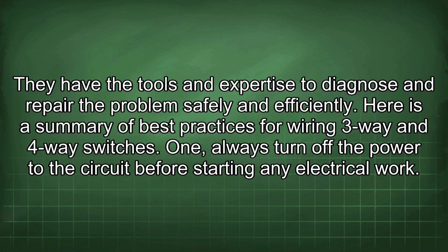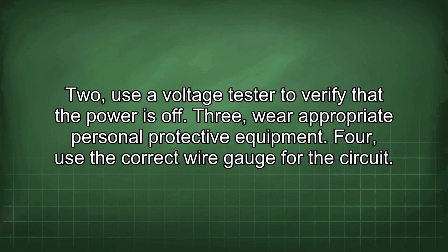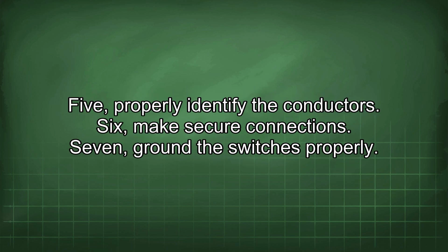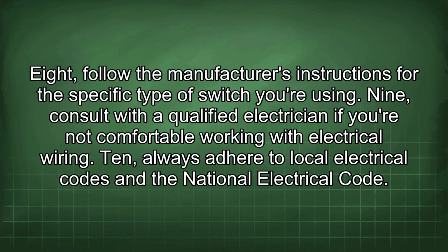Here is a summary of best practices for wiring 3-way and 4-way switches. 1. Always turn off the power to the circuit before starting any electrical work. 2. Use a voltage tester to verify that the power is off. 3. Wear appropriate personal protective equipment. 4. Use the correct wire gauge for the circuit. 5. Properly identify the conductors. 6. Make secure connections. 7. Ground the switches properly. 8. Follow the manufacturer's instructions for the specific type of switch you are using. 9. Consult with a qualified electrician if you're not comfortable working with electrical wiring. 10. Always adhere to local electrical codes and the National Electrical Code.